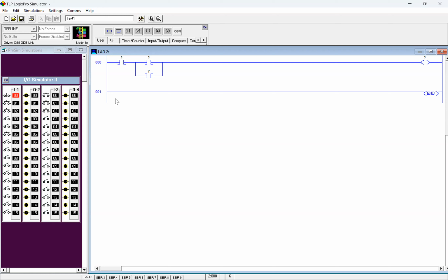So if you really want to do work, you can type all this in, I:0/00, or you can just grab this, drag it up here. When it goes positive with the plus on it, release it. Nice. And then what I do is I make my students right then and there so they don't forget. Right click. In this case, you edit symbol, but in the real one, I do description. I don't use symbols in 5000. And I'm going to call it stop. And edit. All right, cool.